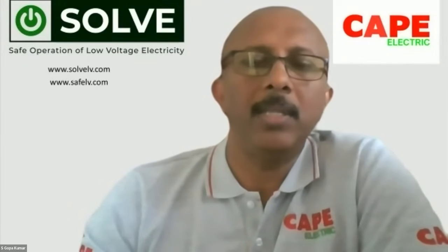You cannot avoid that, saying since my installation is complicated, I don't need to make a verification. That is wrong. Periodic verification will be able to find out the new challenges, which probably were not faced during the initial days of electrical installations. Of course, periodic verification can be done, we are already doing it. In fact, we are making verification, or sometimes some auditor is making it, the hospital is giving us the inputs, and we are guiding them what to test, how to test, when to test, then checking the single line diagrams and guiding the hospital's owners or the engineers in the hospital as well as the auditor to make it perfect or better.